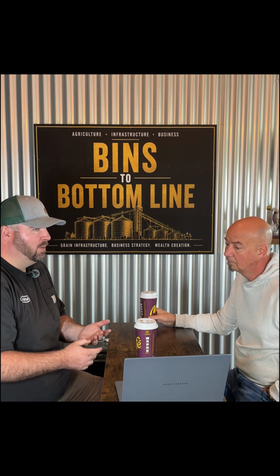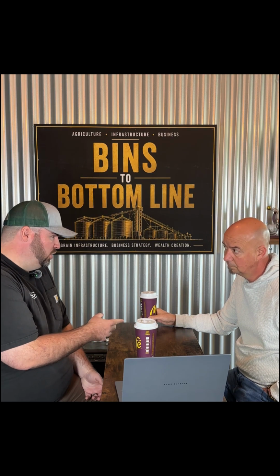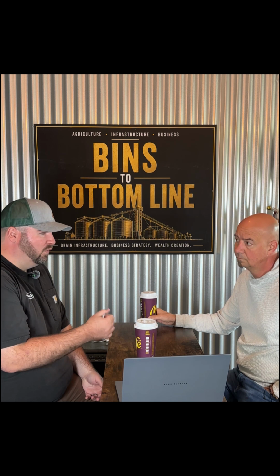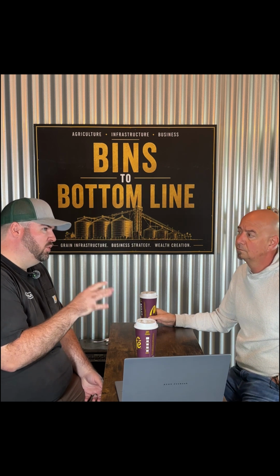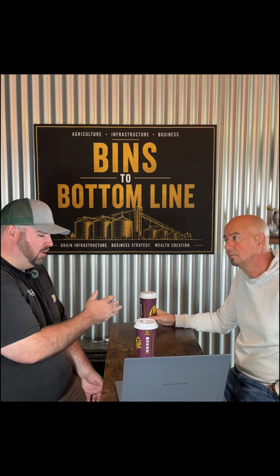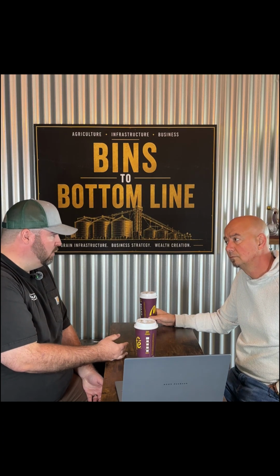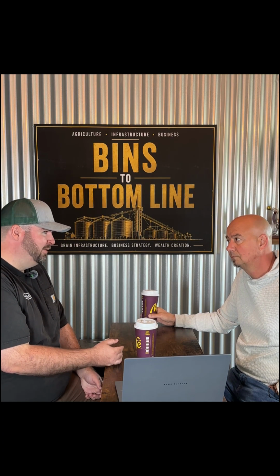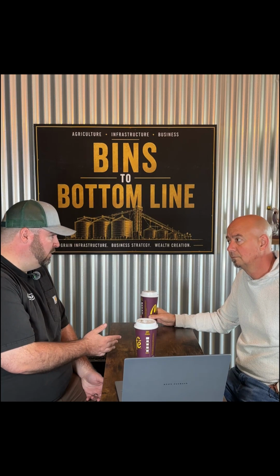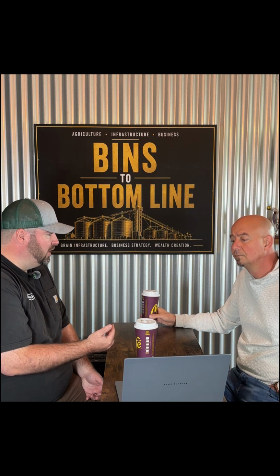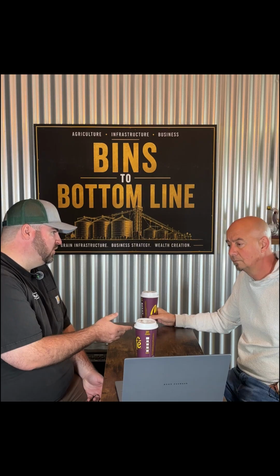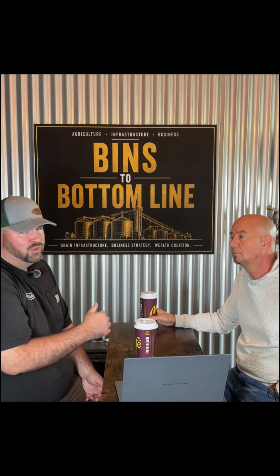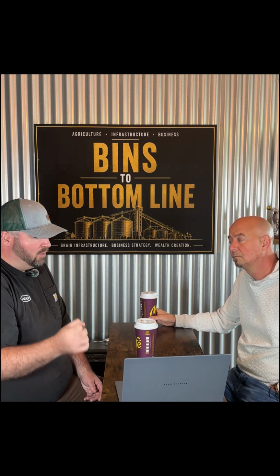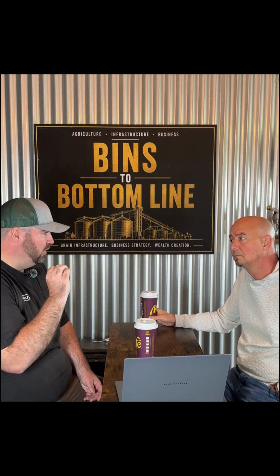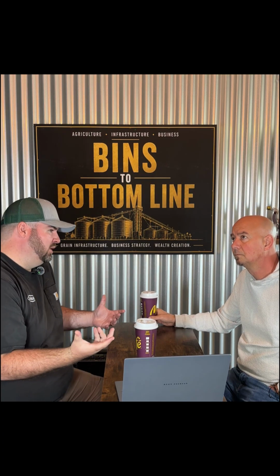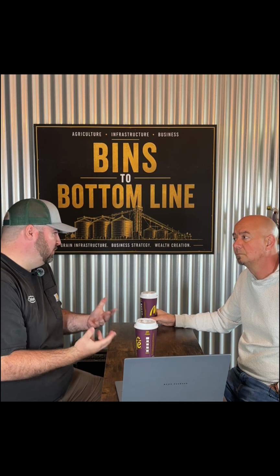In summary, for our workhorse machines, the 3-chute, 4-chute, 5-chute, if it's a 5-chute machine going into a plant, you go 5 chutes times 5 horsepower and add 5. So 5 times 5 is 25, adding an extra 5 horse for extra air, we're putting a 30 horse compressor package in there. You're also going to need a chiller, a dryer because those ejectors need to fire dry air, and a receiving tank to make sure you have some surge capacity.